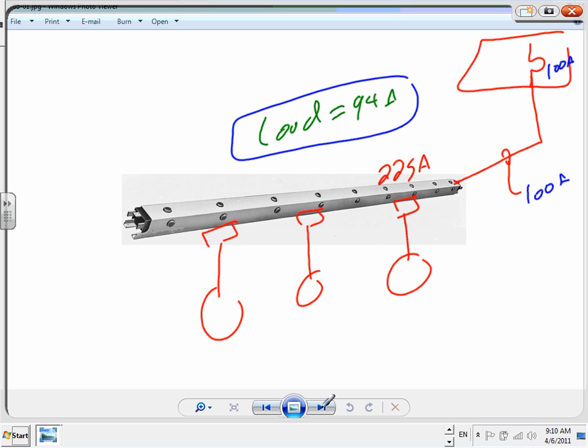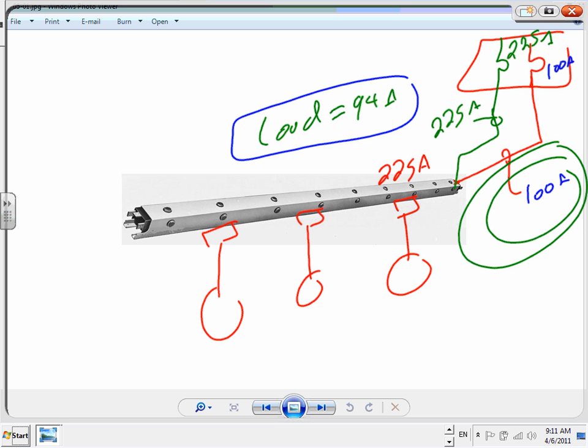Look at the alternative. What's the alternative, guys? The alternative is a 225 amp panel, expensive, tied to here, and this cable a 225 amp cable. I can do that, right? I can do it with a 225 amp circuit breaker feeding a 225 amp cable that feeds a plug-in or a trolley busway. In a case like this, I will vote for the 100 amp feeder and overcurrent protection device. I just want you to be aware of this one. Any questions, guys, about this? So you don't have to match the size of the panel.